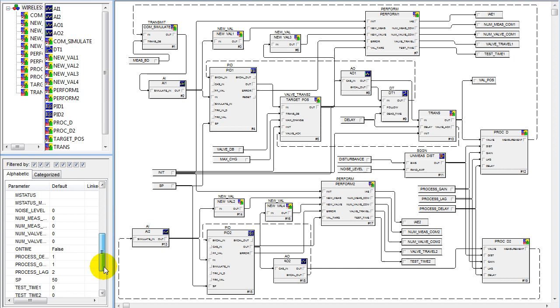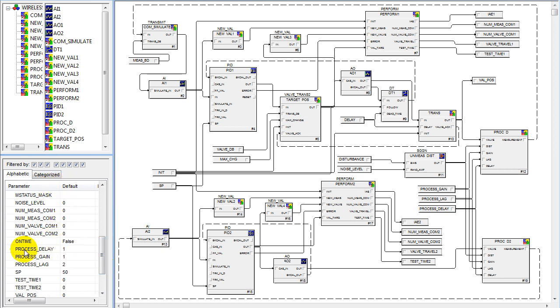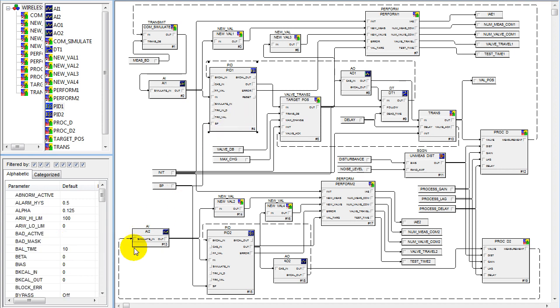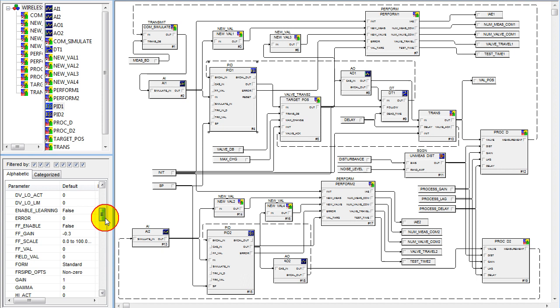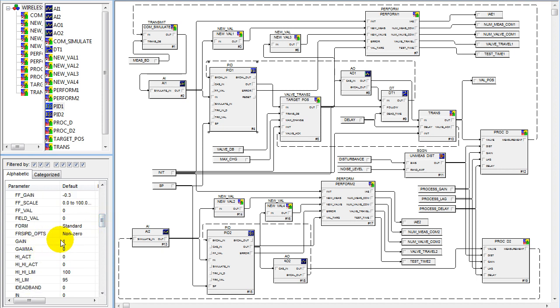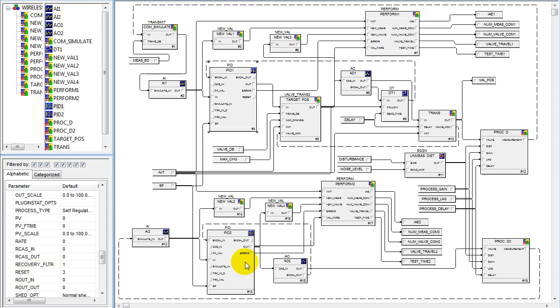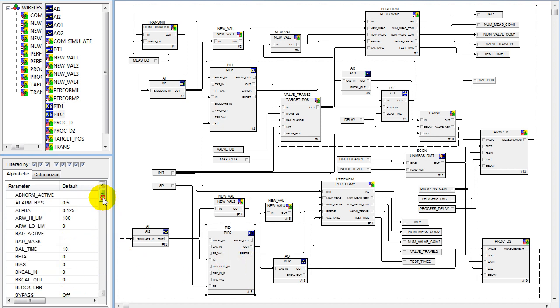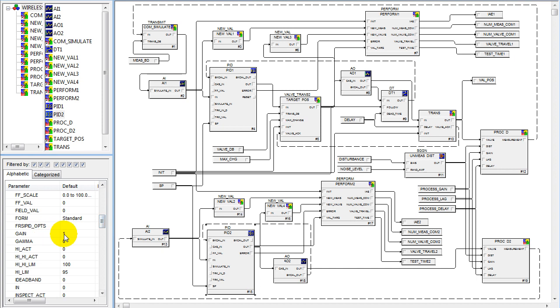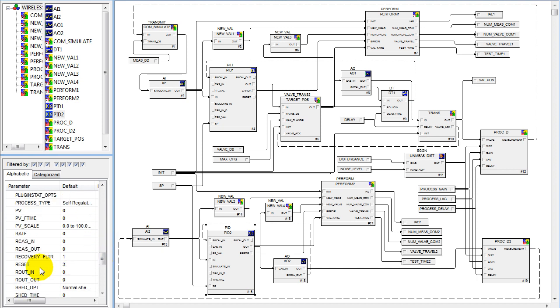The process that we're using is a very fast process — gain of 1, dead time of 1, and a lag of only 2 seconds. The PID Plus tuning is only based upon the process dynamics: gain is set to 1 and reset is set to 3 seconds. The regular PID for wired input and wired output is tuned exactly the same, with a gain of 1 and a reset of 3 seconds.